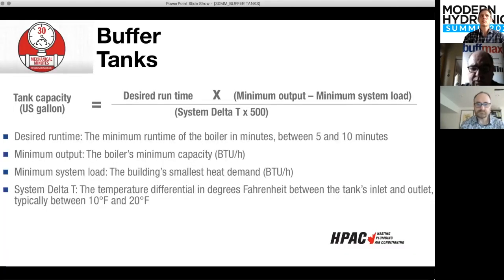Yeah, so basically, as you said, it's part of the system, so you want to utilize it to the fullest. And again, we talk about it's the friend of the boiler. So there is a formula that you should use to size the one. And as Steve mentioned in our conversation, it's never a bad thing to be oversized in a buffer tank. But there is a formula, and it's all about runtime. If that boiler has a short cycle of 10,000 BTUs, 15,000 BTUs, whatever that is, you want to be able to talk between the storage, which is your battery, and the boiler.